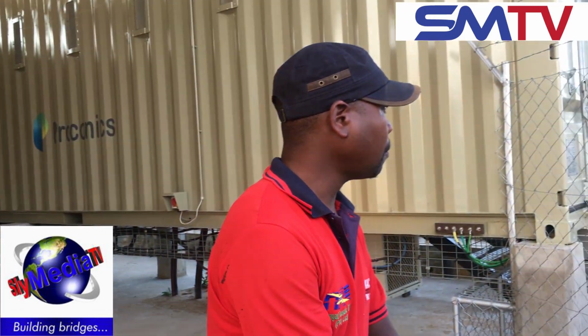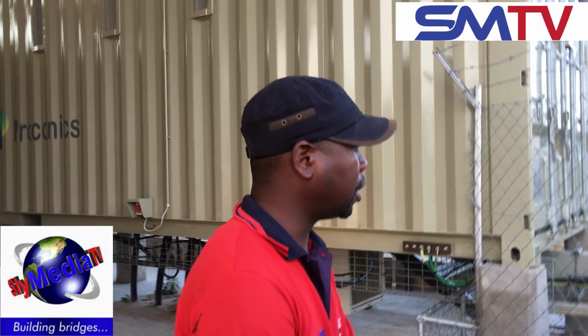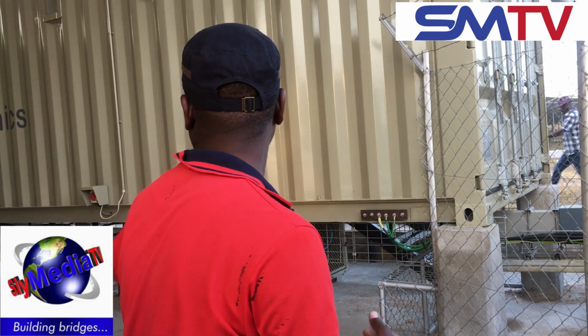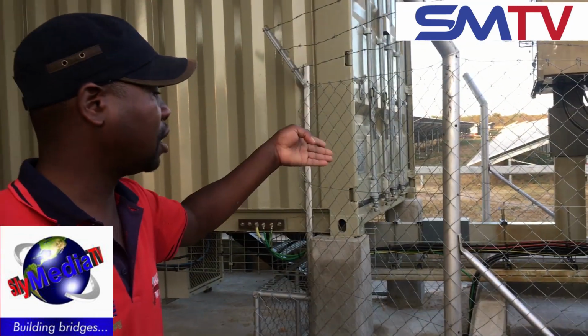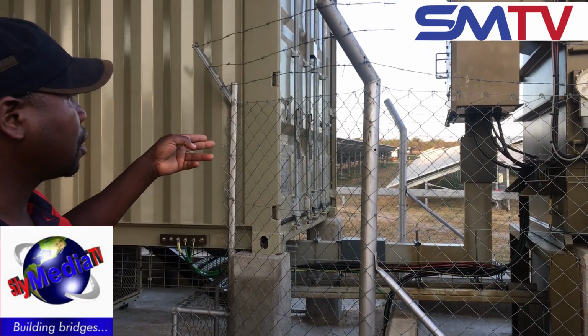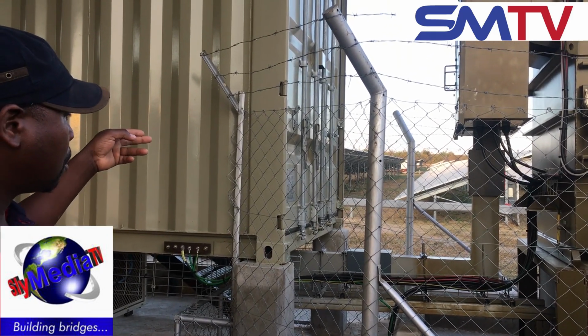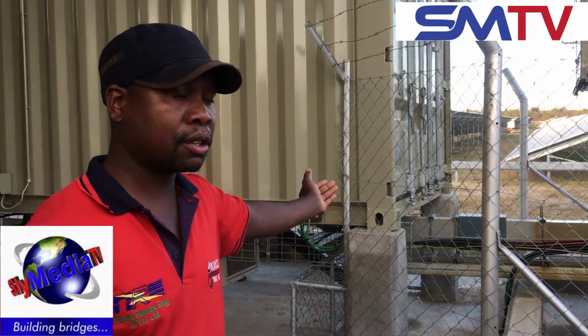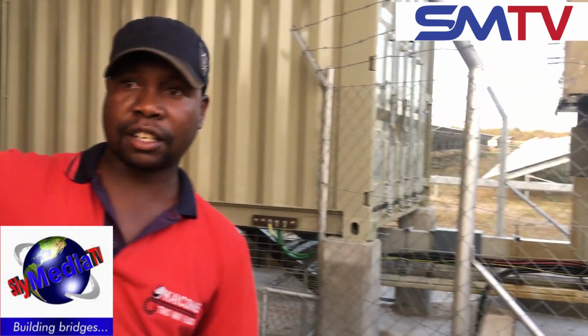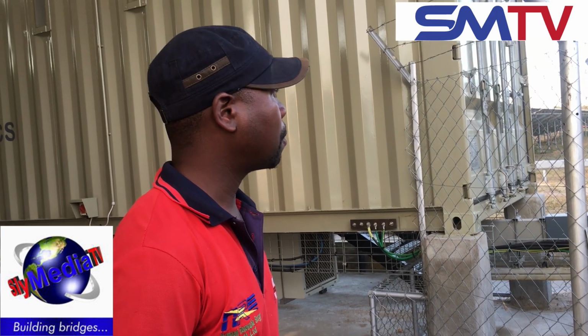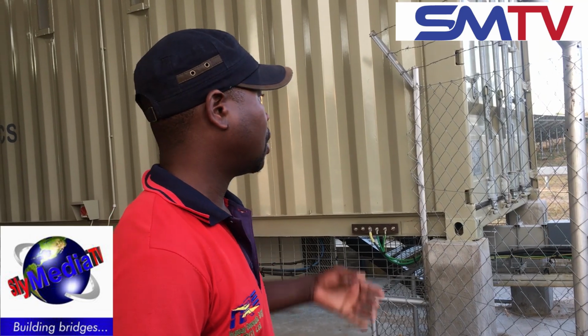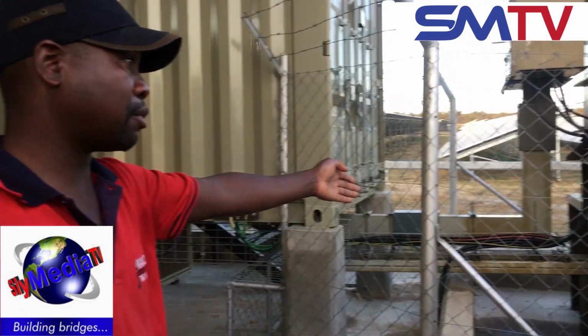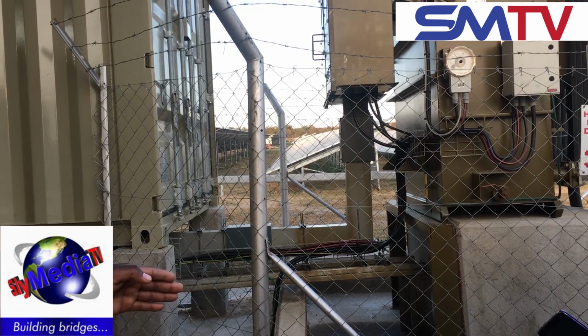Here we've got two transformers, each rated at 1.5 MVA. This side has 20 inverters, and this side has 20 inverters—40 inverters in all. So we generate 400 volts AC, 3-phase, and this is a step-up transformer, from 400 to 33.